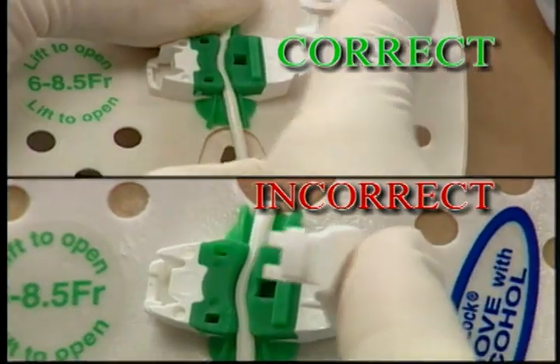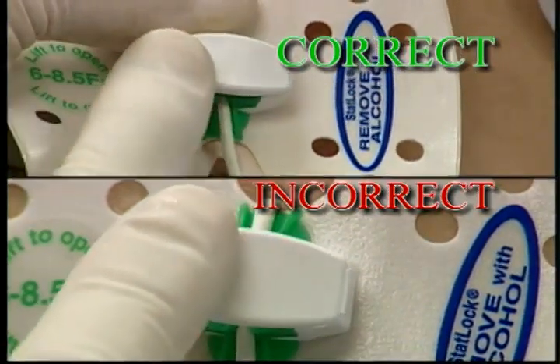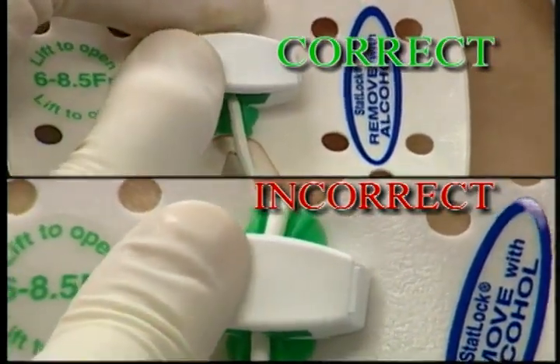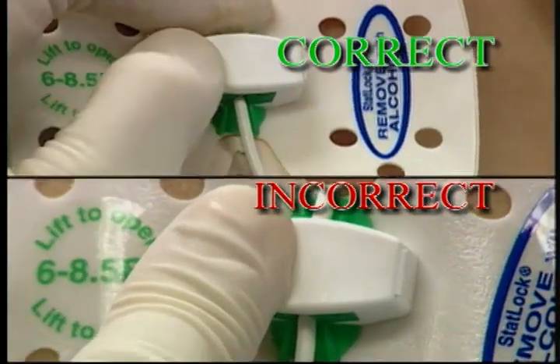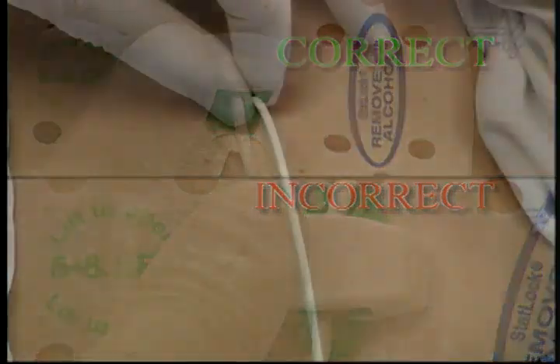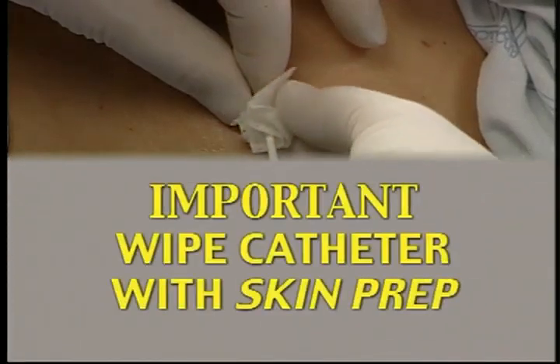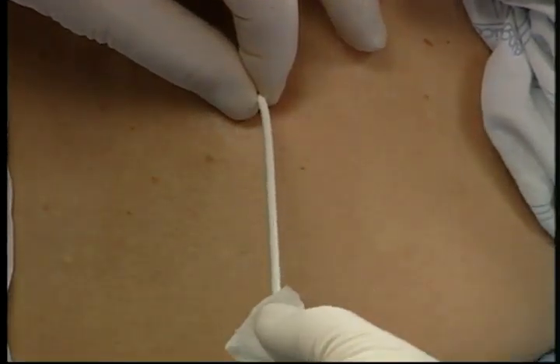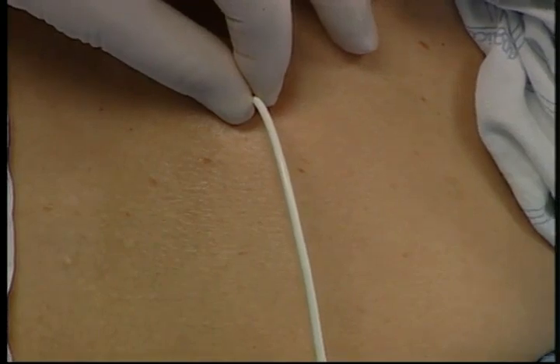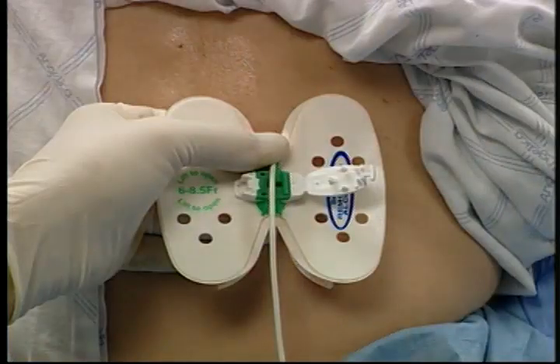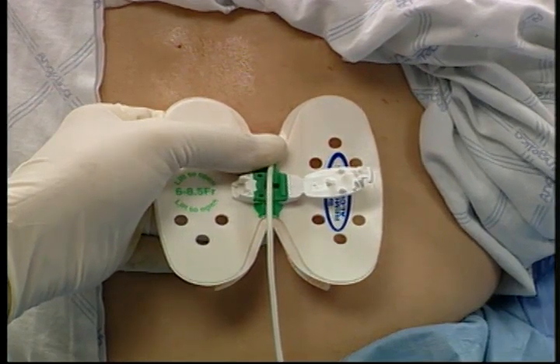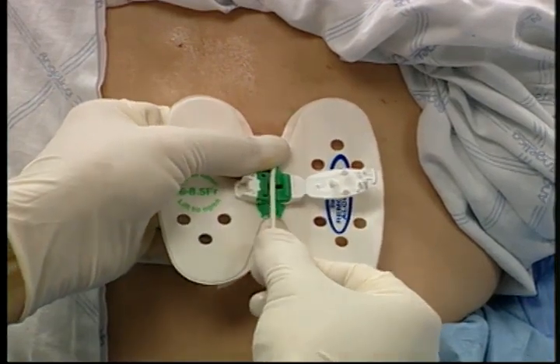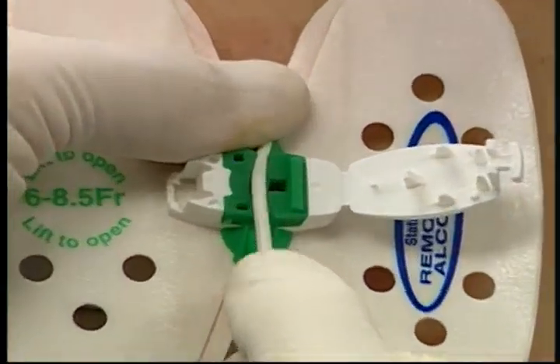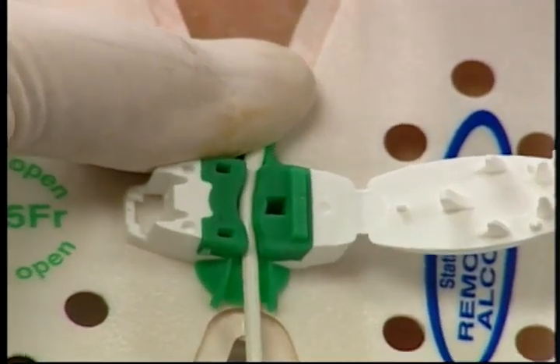To avoid exerting undue pressure on the patient's skin, always press the drainage catheter into the StatLock device retainer before applying the anchor pad to the patient's skin. To accomplish this, first, wipe the skin protectant pad over the exposed portion of the catheter. This will strengthen the StatLock device grip. Then, while it's still wet, hold the catheter firmly between the thumb and index finger of one hand, and using the other hand, tug once to align the catheter. Then, tug once more to seat the catheter deeply into the retainer.